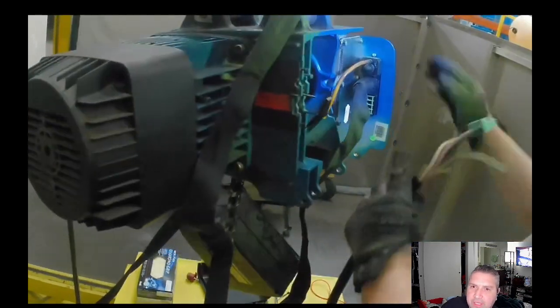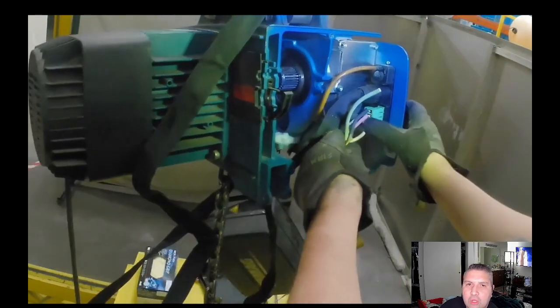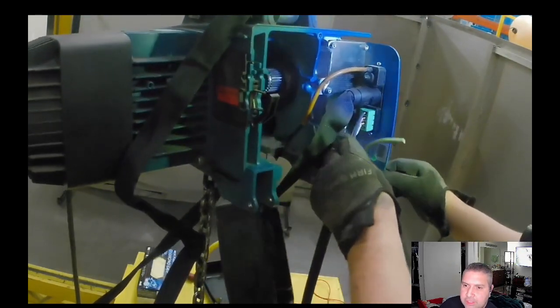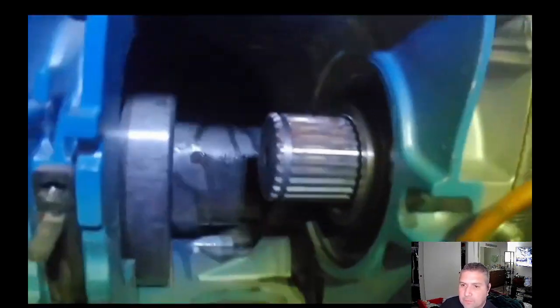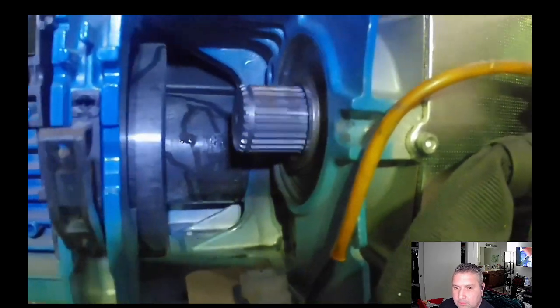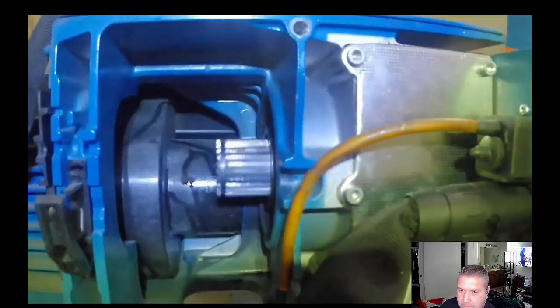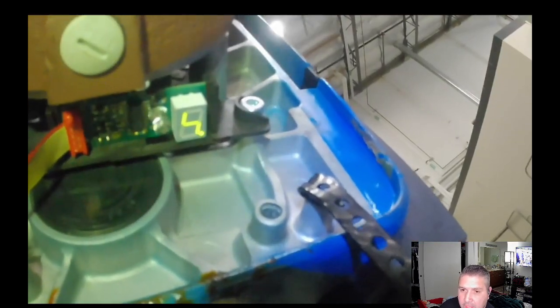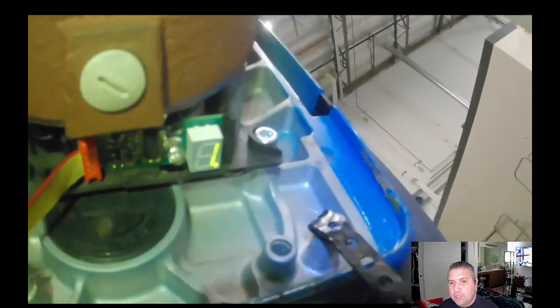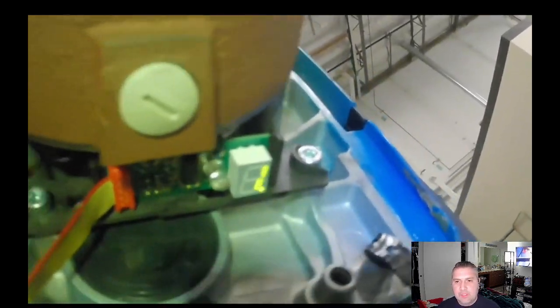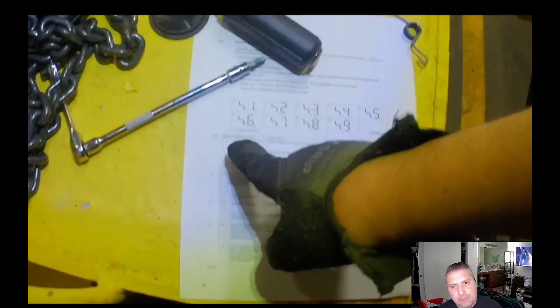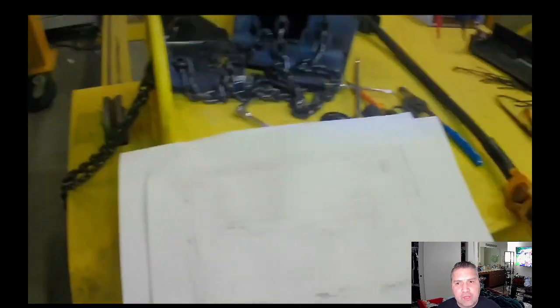I got the chain assembly off, and I'm going to try it now with absolutely no load, so no lifting load and no driving load. It is still running in one direction, and in the other direction it's still giving the fault. So I know it's not in the chain assembly. Now I'm going to narrow my troubleshooting to only the motor, gearbox, or somewhere in that realm.